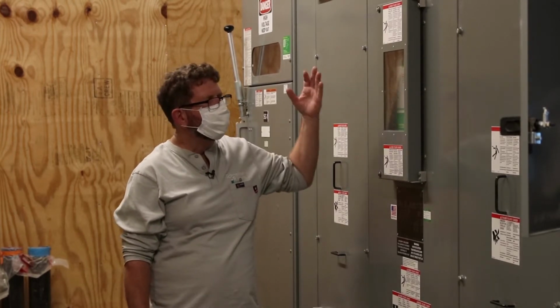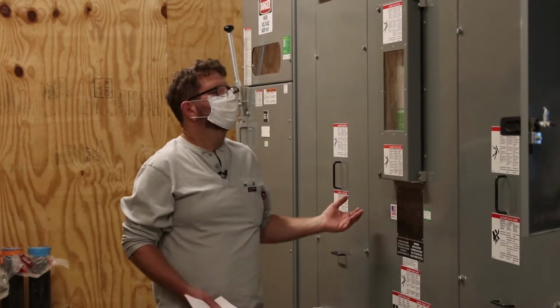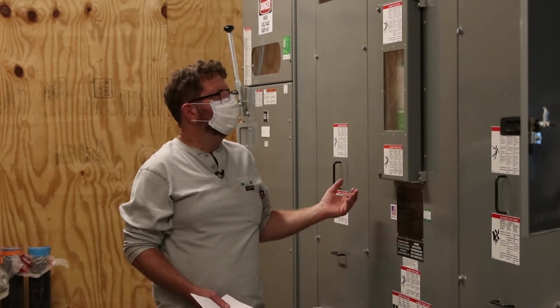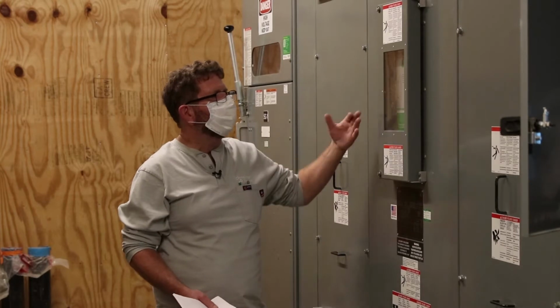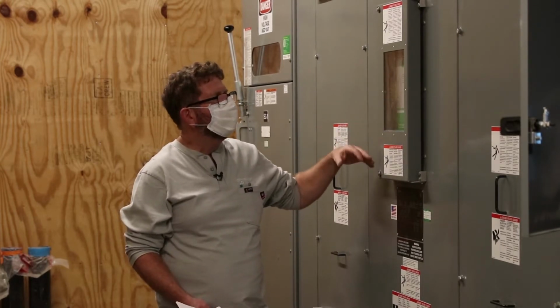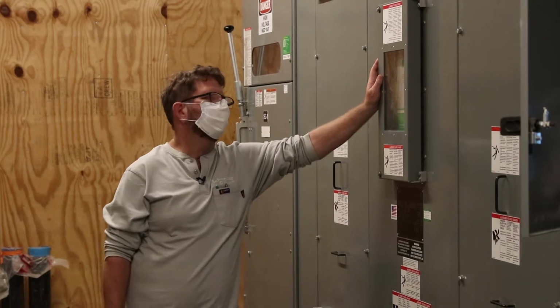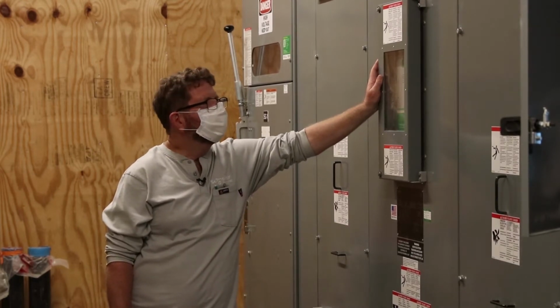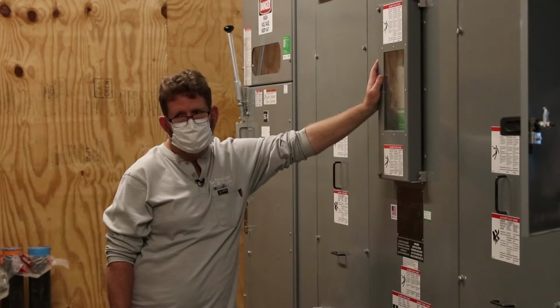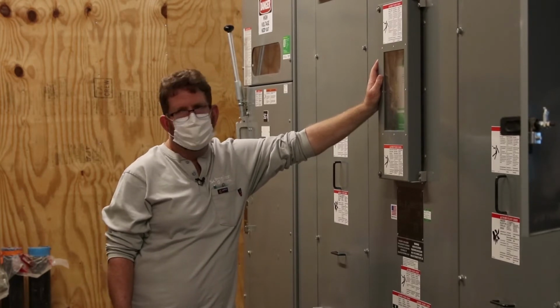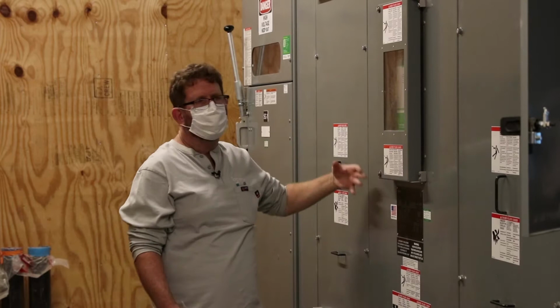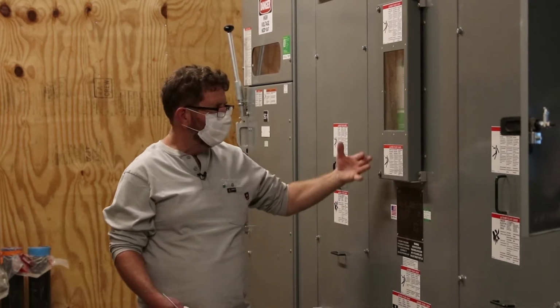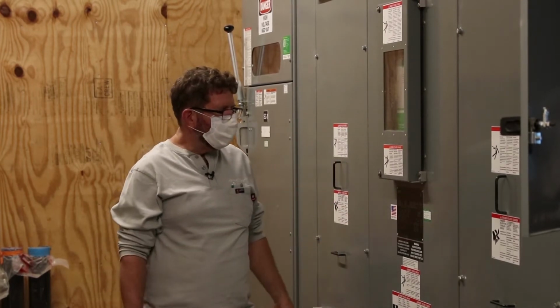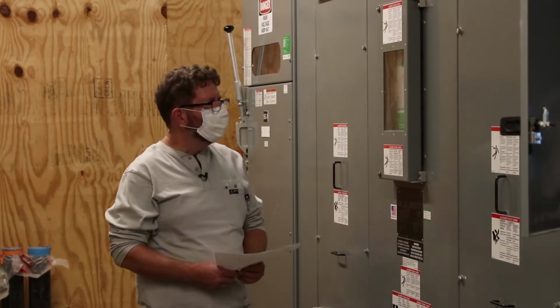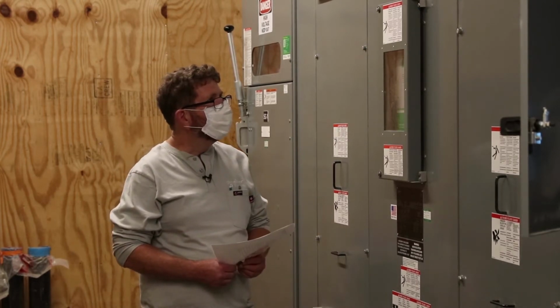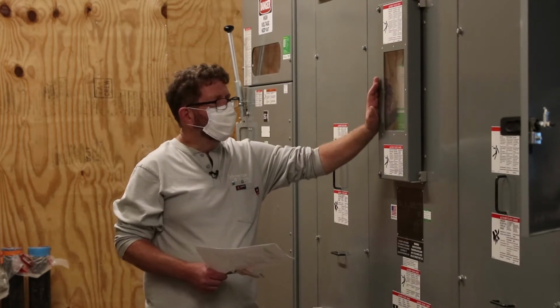You'll have a light that comes on right there where it says fans, that'll show you the fans are running and you'll hear them run. Somewhat above that an alarm will come on. It's an audible and visual alarm, and there's also a trip contact. Trip contactors, I think, runs about 220 degrees Celsius. It's not wired into anything, so nothing's actually going to trip, but if you're into the fan loading of the transformer, you could wire it in to trip the main breaker to unload the transformer.